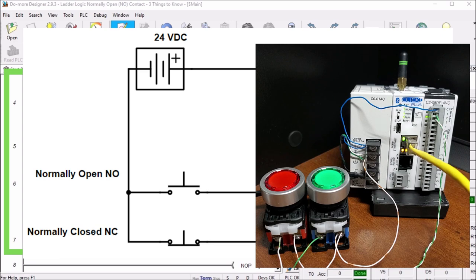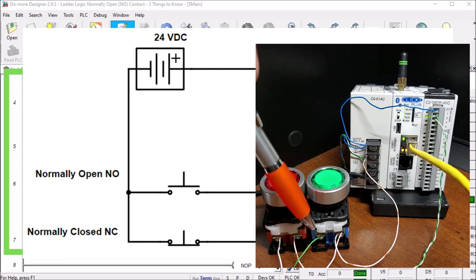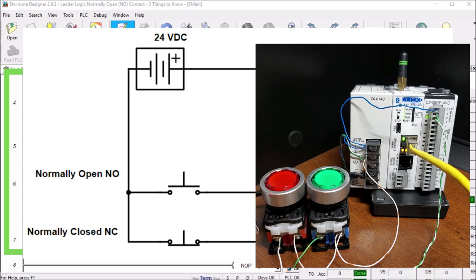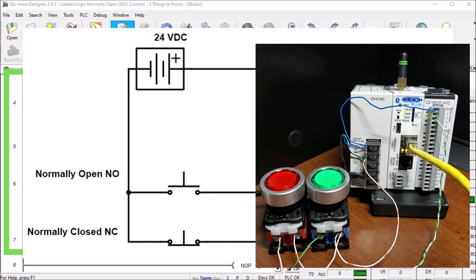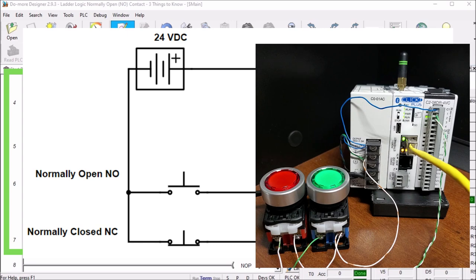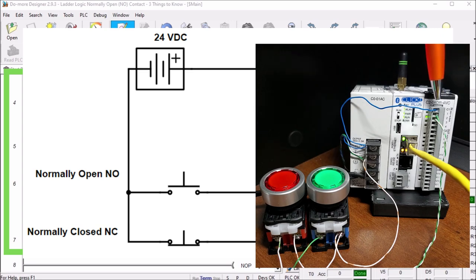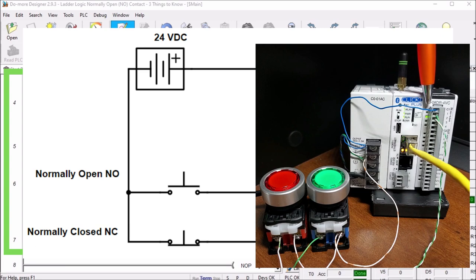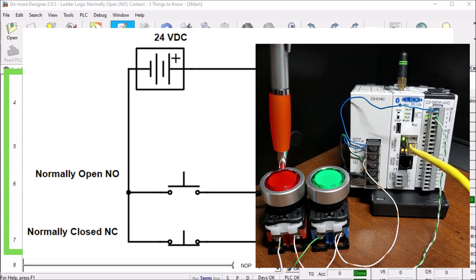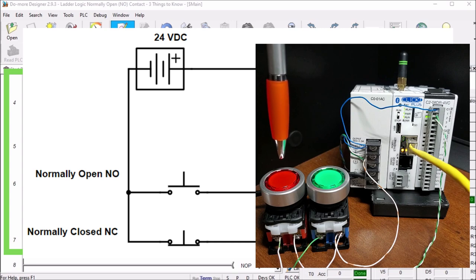You'll notice that normally when we wire things up they are color coded, so this is my normally open contact - it's in blue. My normally closed is in red, and typically any e-stop circuit or stop circuit will always be a normally closed condition. You can see right now because we have voltage onto the input side, my input one does not have any voltage here - it's off. And my input 2 has voltage because we have the normally closed contact coming from our stop signal, so that is on.